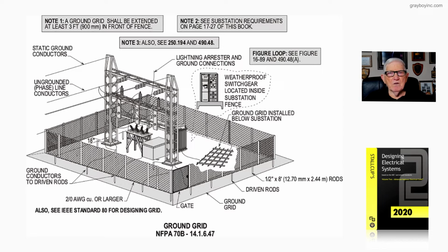And then you have your lightning arrestors and ground connections, which you would find in the new Article 242 in the NEC 2020 edition. So you have your ungrounded conductors coming in, you have your static wire to pick up surges and lightning strikes and divert them through the lightning arrestors into the grid system. And all of your equipment that you see in the substation is connected to that grid system. And that keeps everything at equal potential to ground as you can possibly get it if you're working in the substation.